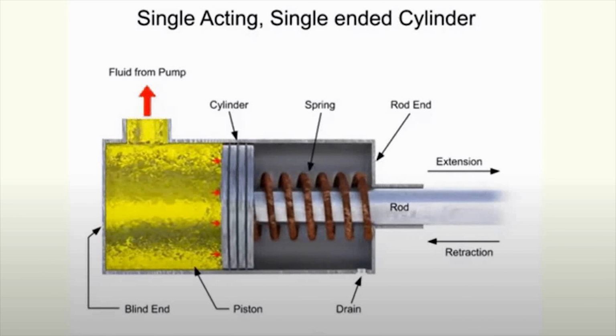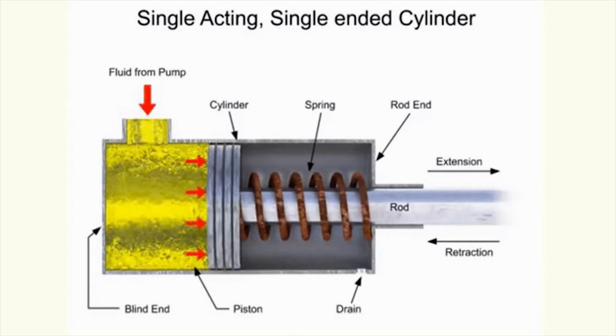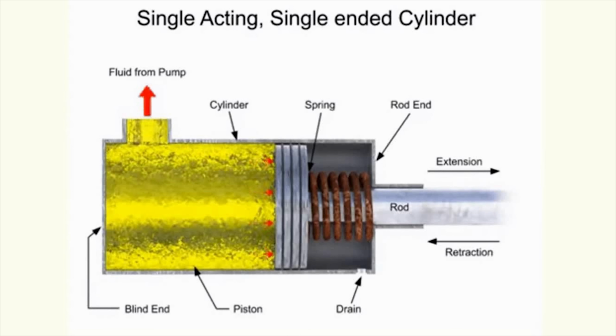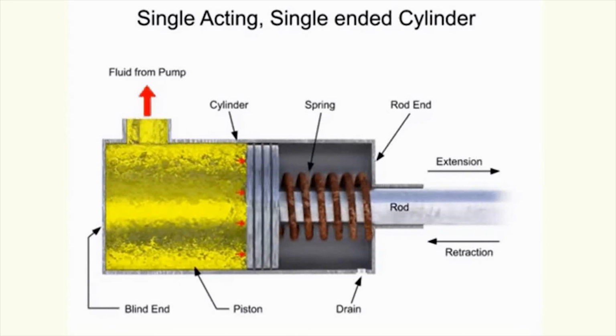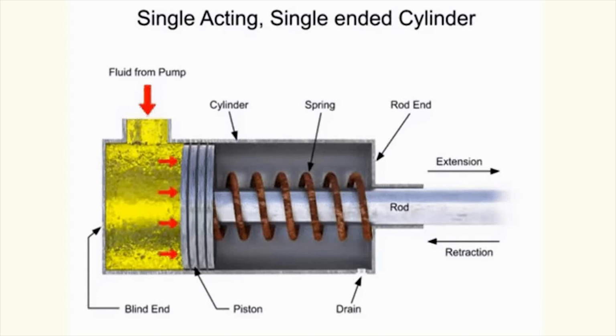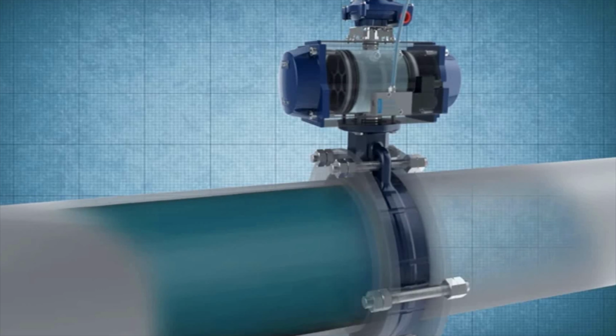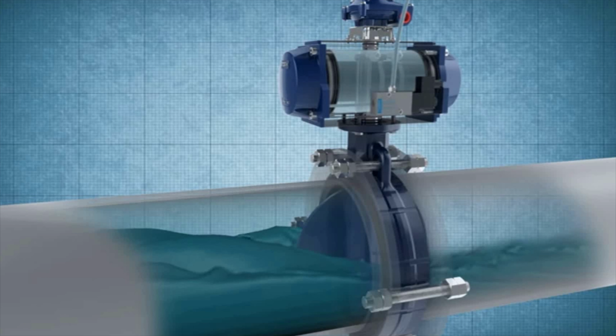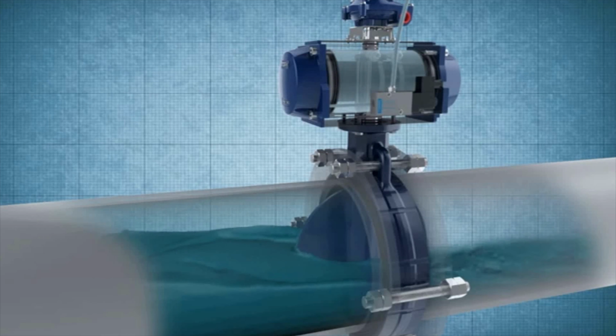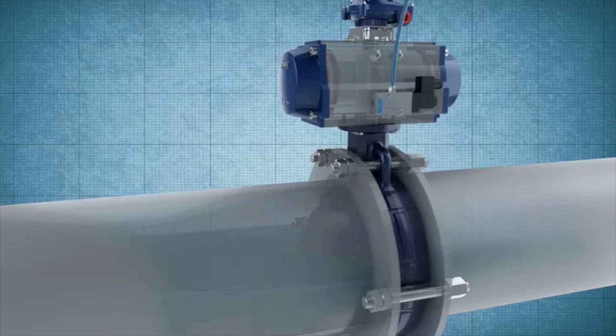Pneumatic actuators. Pneumatic actuators enable considerable forces to be produced from relatively small pressure changes. Pneumatic energy is desirable for main engine controls because it can quickly respond in starting and stopping as the power source does not need to be stored in reserve for operation. Moreover, pneumatic actuators are cheaper and often more powerful than other actuators. These forces are often used with valves to move diaphragms to affect the flow of air through the valve.